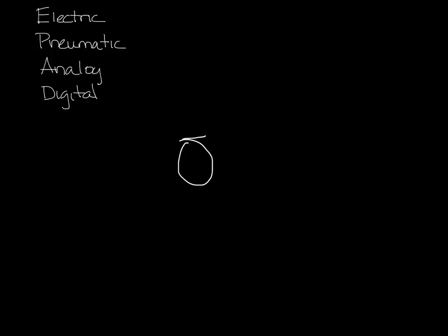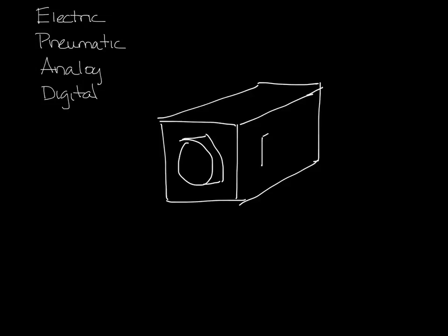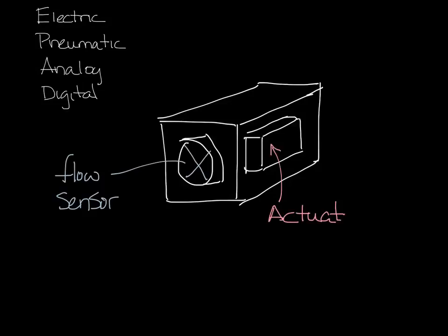So let's draw a single duct box. Here's the inlet and the casing. Draw on a control box. Okay, so there's a flow sensor in the inlet of the box measuring the flow. Inside the control box there's an actuator that opens and closes the damper and a controller that controls the actuator's operation.